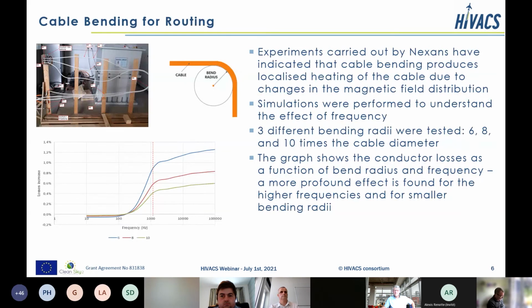Another thing that was looked at in some detail was the impact of bends. Compared with cables that you would normally find on a ground-based power system, cables in an aircraft will go through much tighter bends. And we wanted to understand what the impact of those bends could be on the thermal radius. So what you can see in the bottom left is a prediction of the losses in a cable as it goes through 3 different bend radiuses.